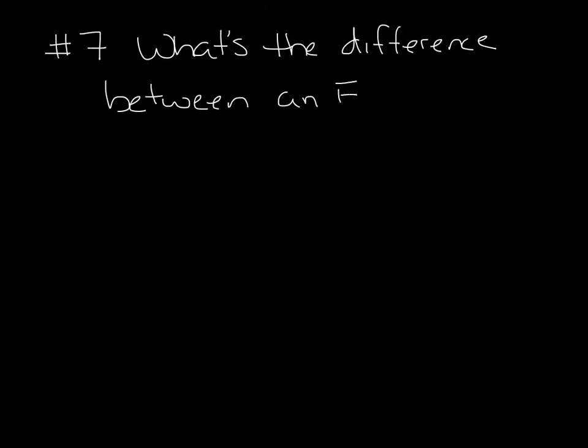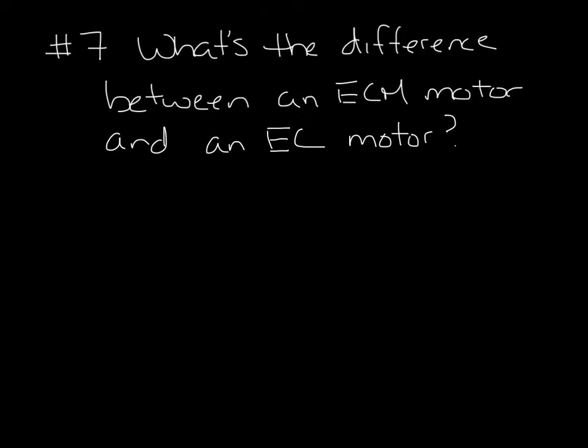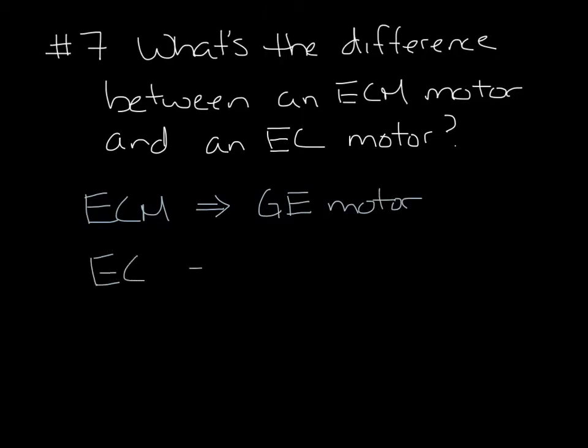Question 7. What's the difference between an ECM motor and an EC motor? They both refer to electronically commutated motors. Originally, the ECM motor was developed, patented, and trademarked by GE. During this time, we started putting them on fan boxes and the name ECM stuck with fan boxes. But later, other manufacturers started making the motor, but they couldn't use the name, so they called them EC motors. So GE motors, which are now Genteq motors, are still called ECM, and everyone else's are called EC, but they're similar technologies.